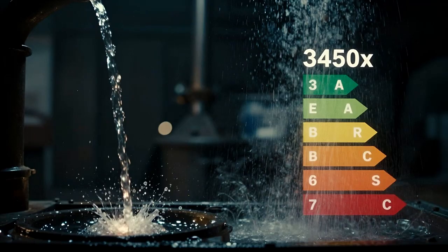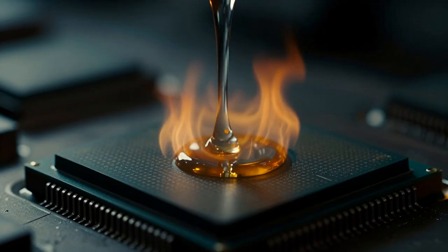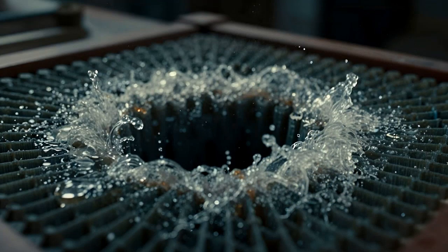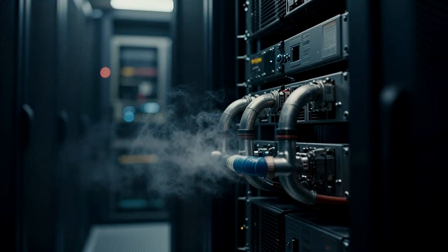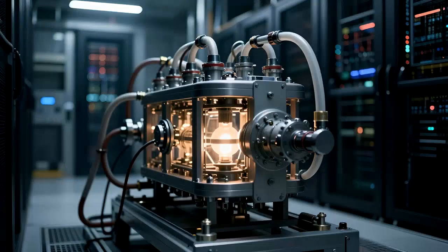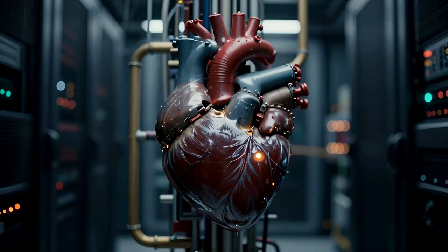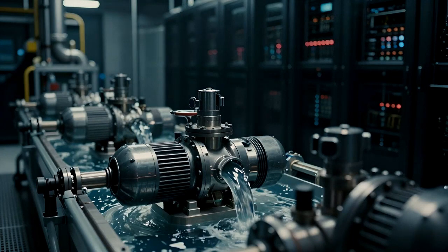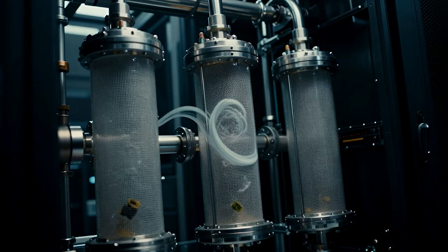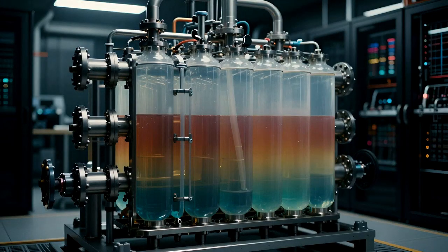Because liquid is 3,450 times more effective at absorbing heat volumetrically than air, the fluid instantly strips the thermal energy away from the silicon as it rapidly flows through the microchannels. The now heated liquid is pushed out of the server chassis and into a critical piece of infrastructure known as a coolant distribution unit. This unit is the beating, mechanical heart of the liquid cooling architecture. It houses heavy-duty redundant pumps, cross-connected filtration mechanisms to catch debris, and a highly efficient liquid-to-liquid plate heat exchanger.